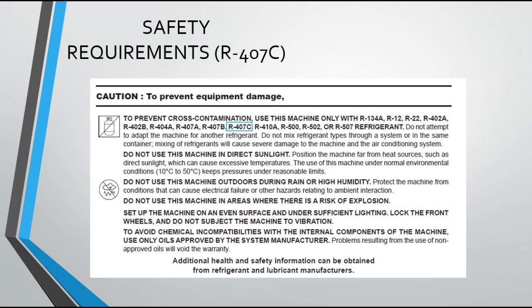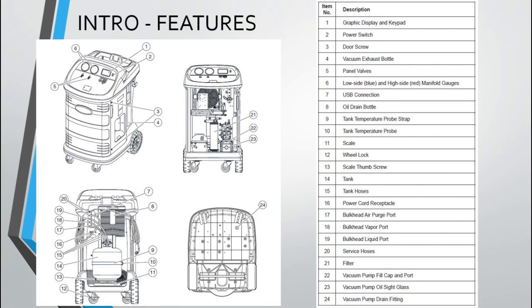Lubricant requirements. Only new lubricant, as specified by the system manufacturer, shall be installed in the AC system. Lubricant removed from the system and/or the equipment shall be disposed of in accordance with applicable federal, state, and local procedures and regulations. Please note the technical specifications. See the feature callouts in the diagram for where main components are shown.